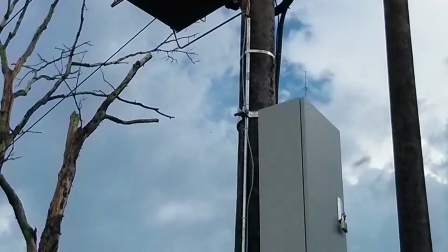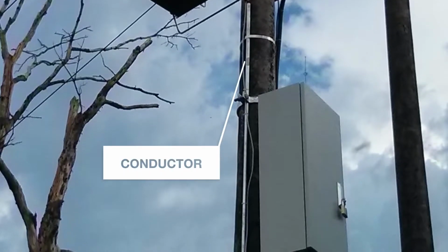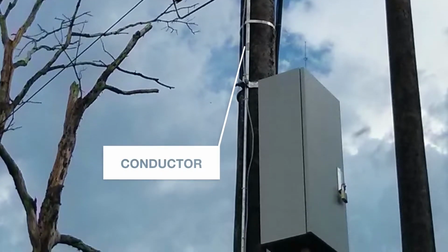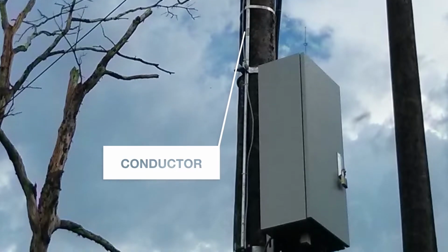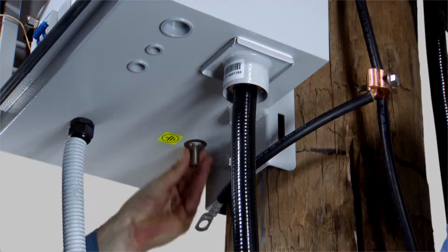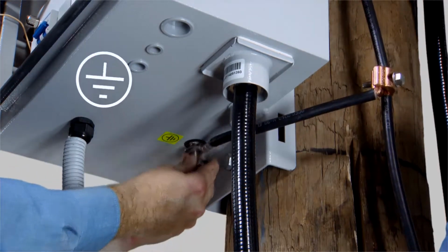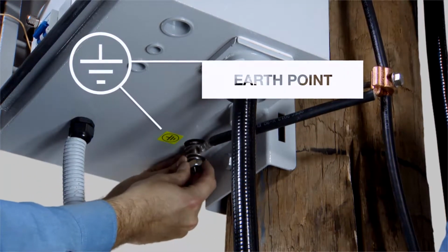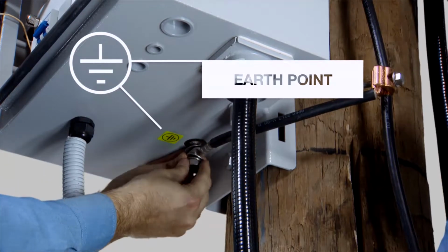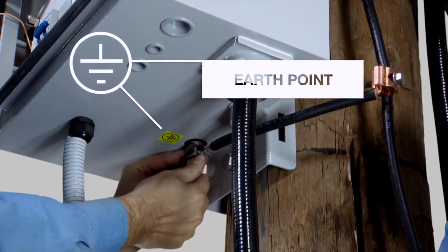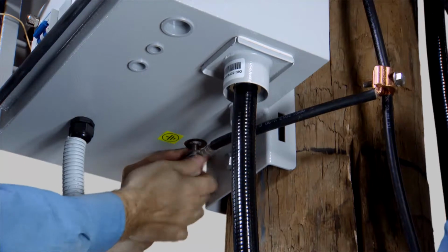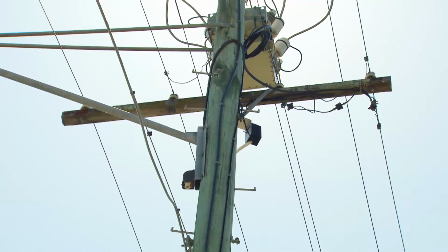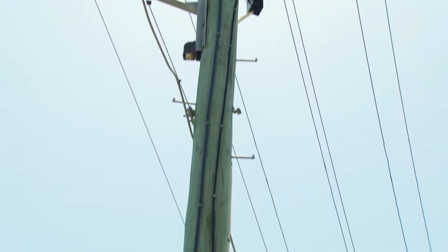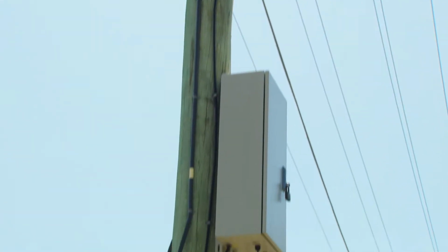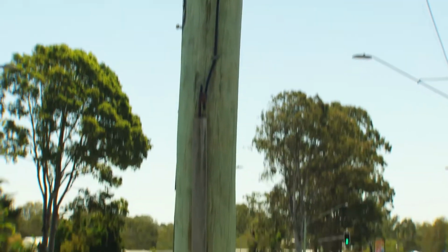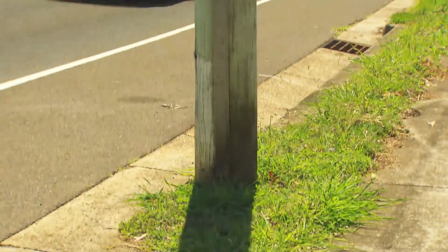In areas with a high risk of vandalism or theft, the conductor can be run inside the pole or through external protection such as a metal pipe. Connect the control cubicle to the main earth using a short length of 35mm square cable and a line tap. Resistance to earth must be maintained within your local regulations for the installation of this type of equipment. The earthing conductor must be unbroken from the recloser to the earthing point at the base of the pole.